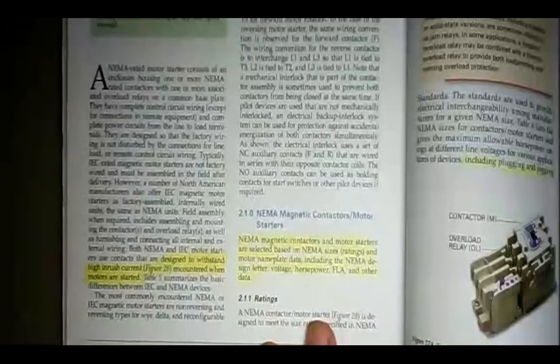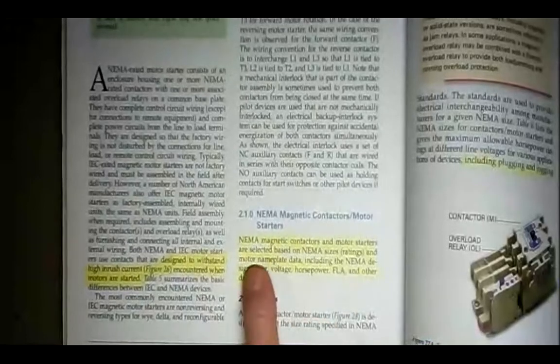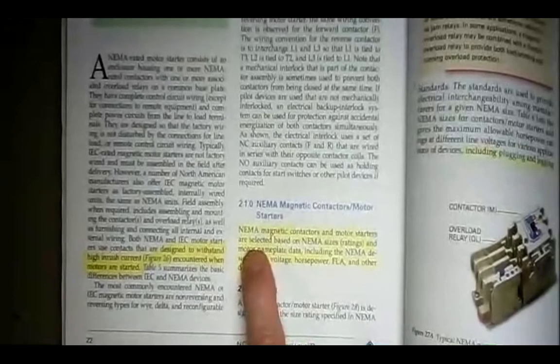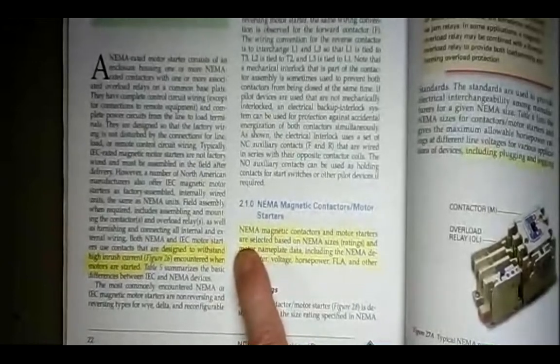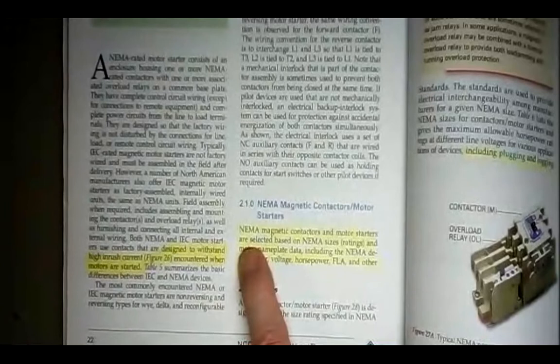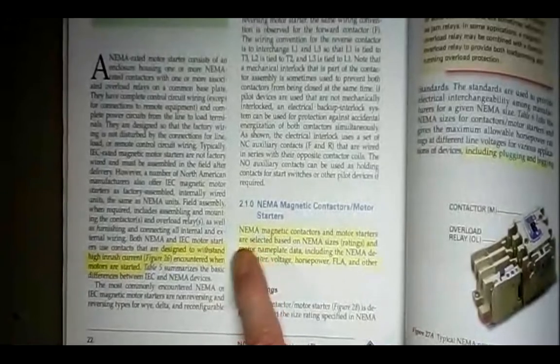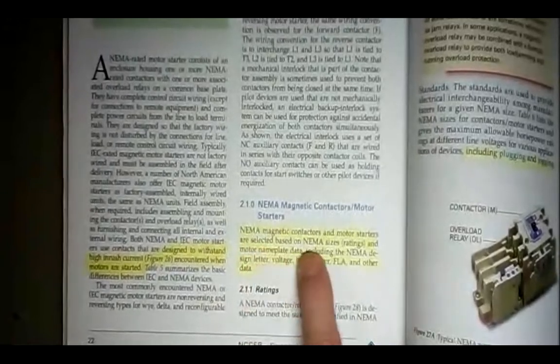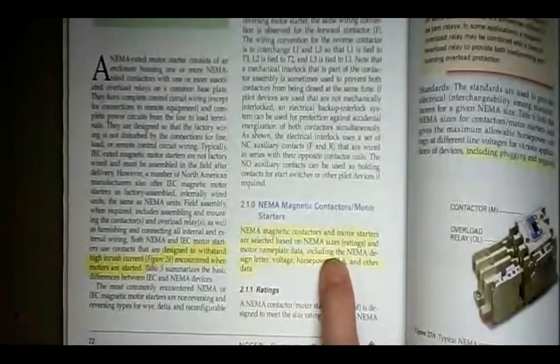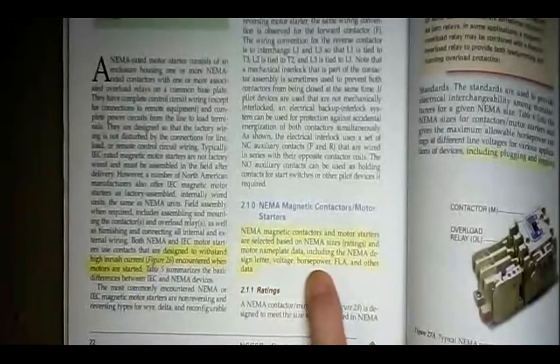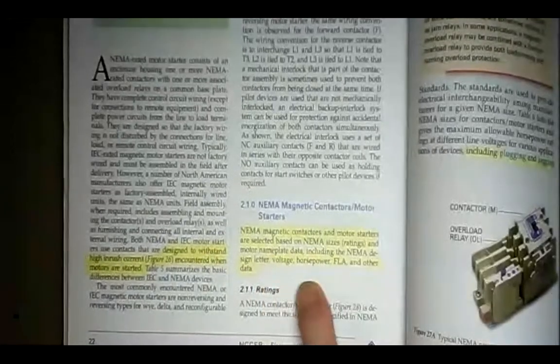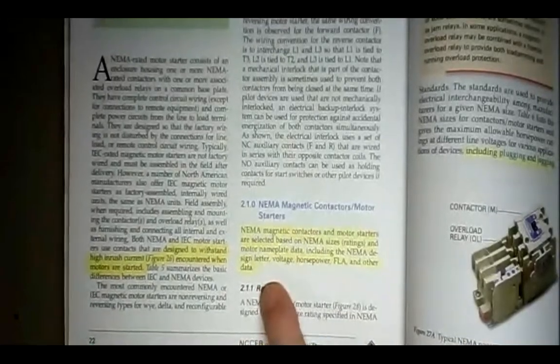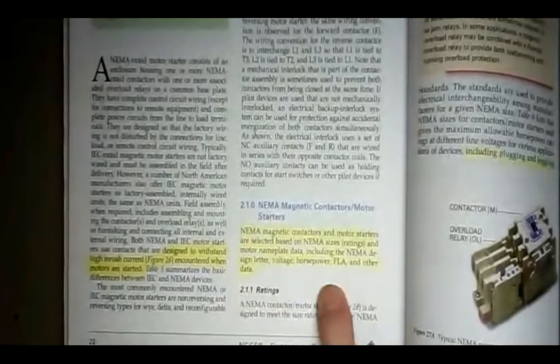On the right-hand side of page 22, very bottom of the page, it says that NEMA, the National Electrical Manufacturers Association, standardizes things like what a 110 volt 15 amp receptacle will look like, what a 110 volt 20 amp receptacle will look like. They set those standards. Magnetic contactors and motor starters are selected based on the NEMA sizes, the ratings, and the motor nameplate data, including the NEMA design letter, voltage, horsepower, full load amps, and other data. All of that data should be on the nameplate of the motor, and you can select your starter based on that information.